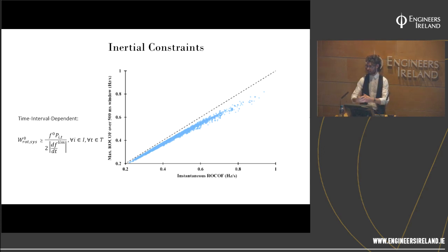Same with moment of inertia. About what axis are you talking about? Because the answer changes if it's a different measurement window. Okay, but because this is a linear approximation that we have here, it's always going to be the worst case scenario. So the constraint is going to bind for a limit that's slightly, it sees a RoCoF that's slightly greater than what the protection settings would see over 500 milliseconds. So within this constraint, there's an inherent safety factor, which increases as the RoCoF increases. So there's kind of an inherent engineering safety factor due to the linearization.